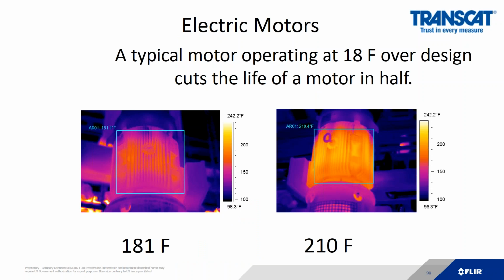Motors are a good source for heat. Infrared is a complementary technology to vibration. If you do any vibration analysis, there's a pretty good chance you already have an infrared camera. In this case, 18 degrees Fahrenheit over on the outside of the motor.